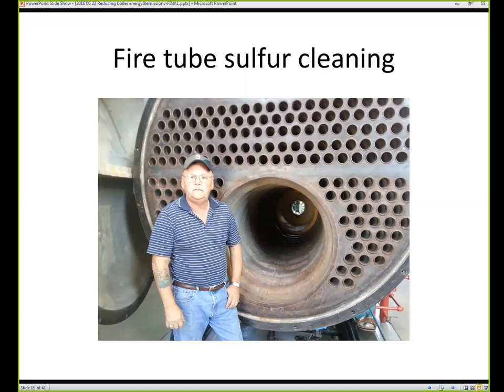Okay, to care for your Morrison tube and to get better heat transfer, just be careful when you're doing this. Take soap and water, a minor amount, and clean just the Morrison tube part of it. The buildup will come off, and you'll notice anywhere from 2 to 5 degrees difference in your stack temp when you do that. Clean it off, and then if you feel like it after you've got it all cleaned, use a light coat of number 2 diesel fuel to keep from getting any rust. We also do all our own refractory repairs and preventive maintenance. We coat our burner throats with Plistix when we open them up for annual inspections. Next.